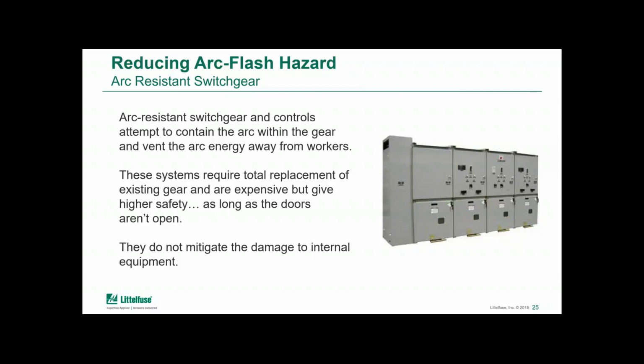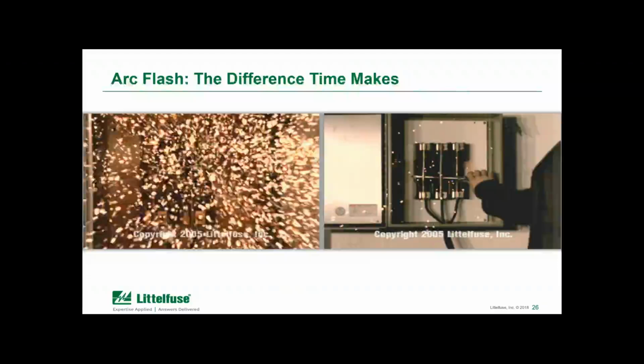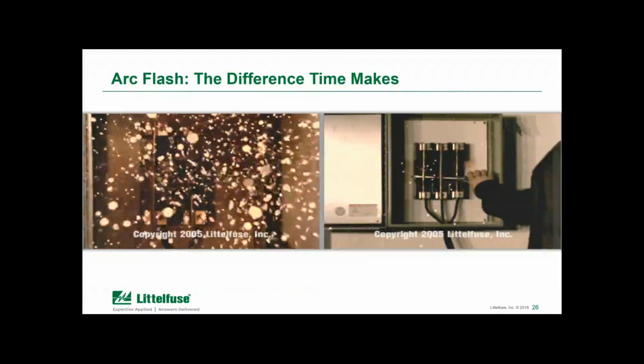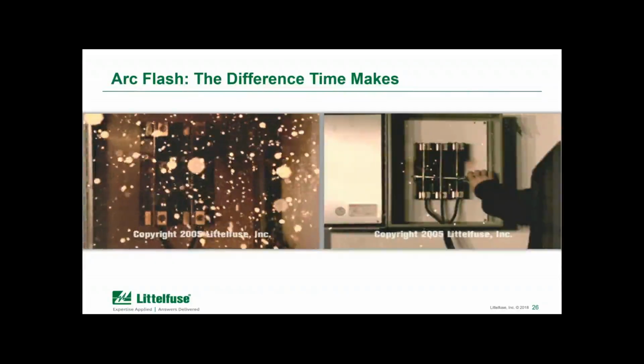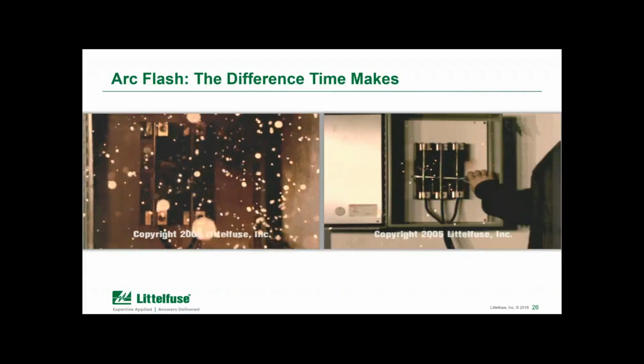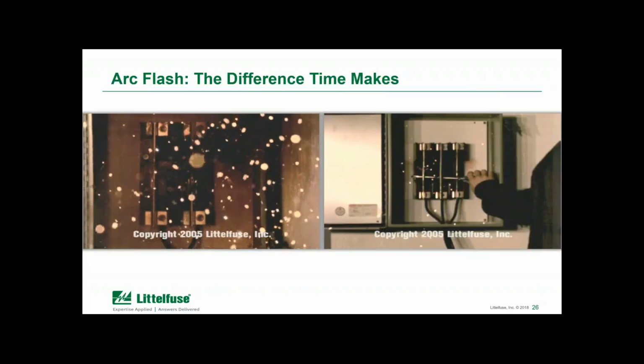Now when the arc is contained inside the equipment, damage can be considerable as well. Now, of course, that is secondary to human life and to the safety of the personnel that are working with the equipment. But it is worthy to note that if a door is open during an event, then of course the additional protection of the arc resistant gear is negated. Now here there's a video that's hopefully coming through all right, but really when we review some of those options, we're kind of coming back to the time again, and that's really not a consolation prize.